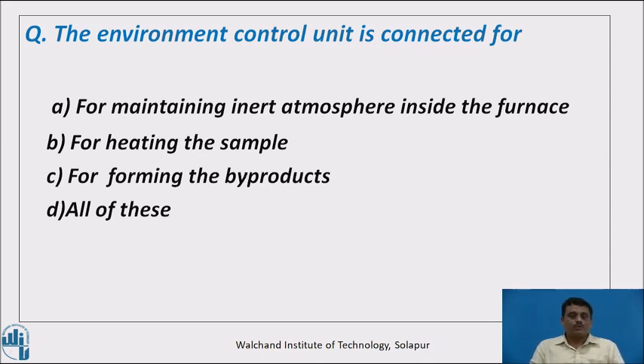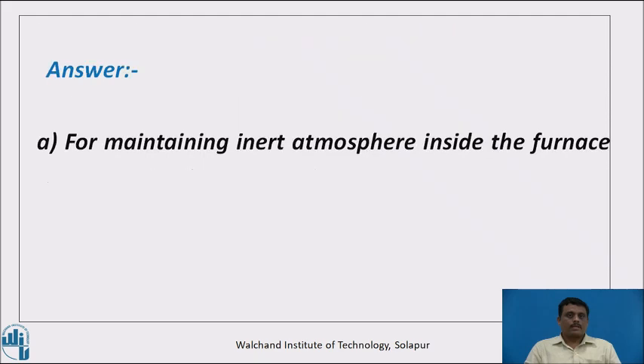Here is a question: the environment control unit is connected for — option A: maintaining inert atmosphere inside the furnace; option B: heating the sample; option C: forming by-products; option D: all of these. The correct answer is option A — the environment control equipment is provided for maintaining an inert atmosphere inside the furnace to avoid chemical reactivity of the sample with the atmosphere.